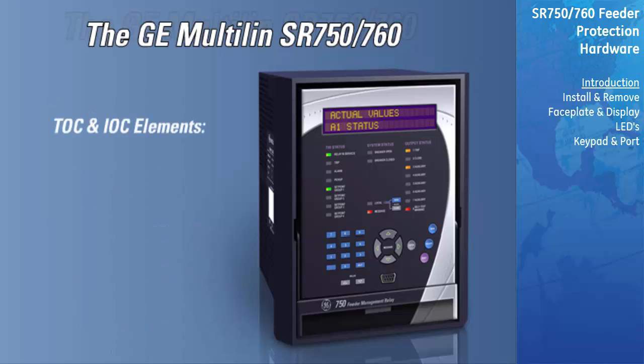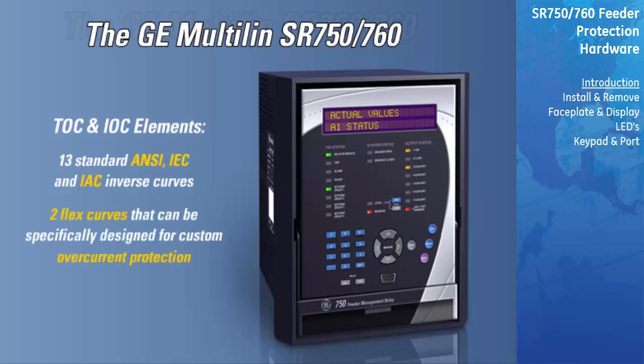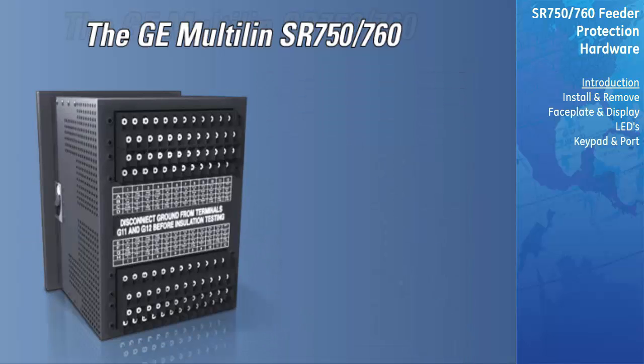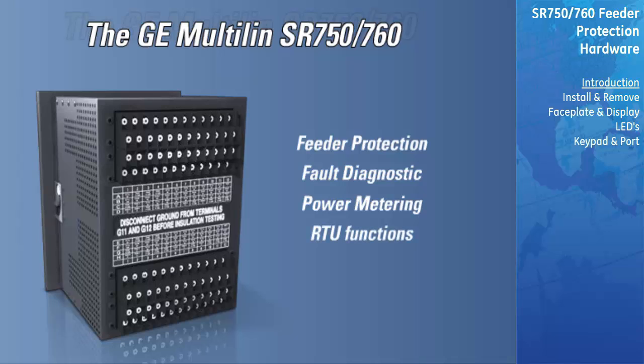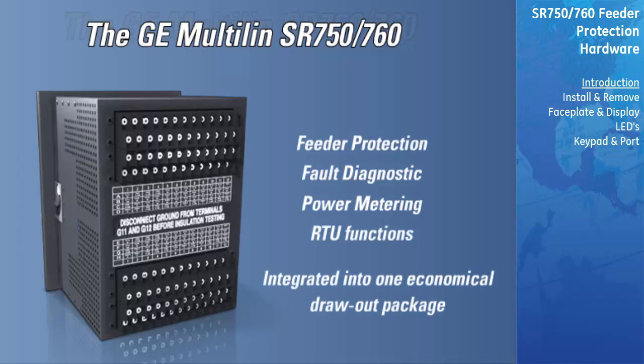The overcurrent protection includes multiple timed and instantaneous elements that incorporate directional control. In addition to the 13 standard ANSI, IEC, and IAC inverse curves, the SR750 and 760 offer 2 flex curves that can be specifically designed for custom overcurrent protection. Feeder protection, fault diagnostics, power metering, and RTU functions are integrated into one economical draw-out package.